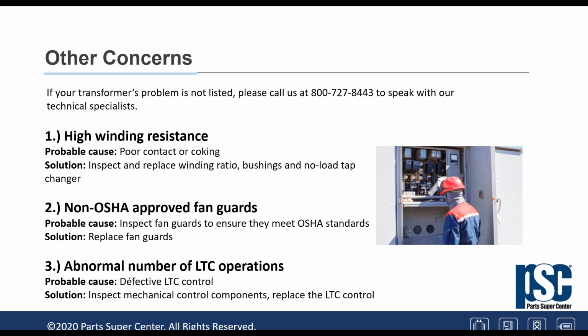So also it could be, like it says here, coking. Again, if there is a poor contact, it's going to create some carbonization there, and it's going to build up. And again, the carbonization will increase the value of the resistance. So, again, we have to investigate why, but usually that's what happens.